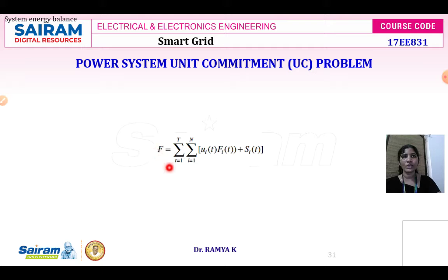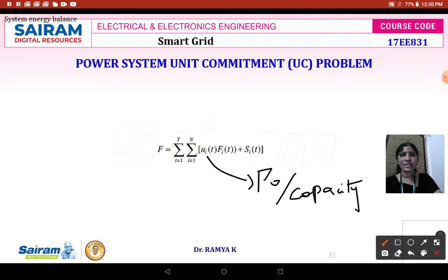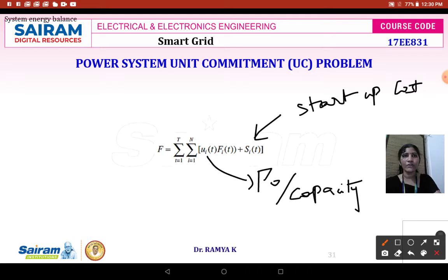The mathematical formula is: f equals summation t equals 1 to T, summation i equals 1 to N, ui(t) times fi(t) plus si(t). Here ui(t) is the ratio of your generation output to your capacity. si(t) is the startup cost of the ith unit at hour t. fi(t) is the fuel cost for the ith unit. N is the total number of units and T is the total time under which unit commitment is performed.